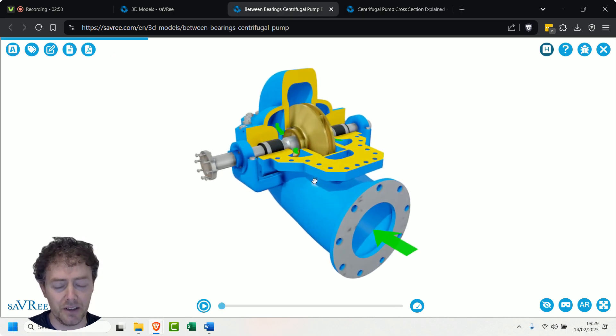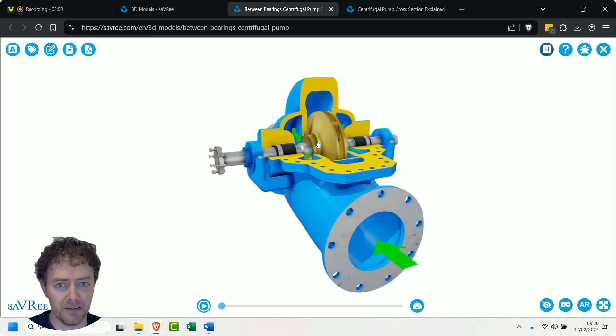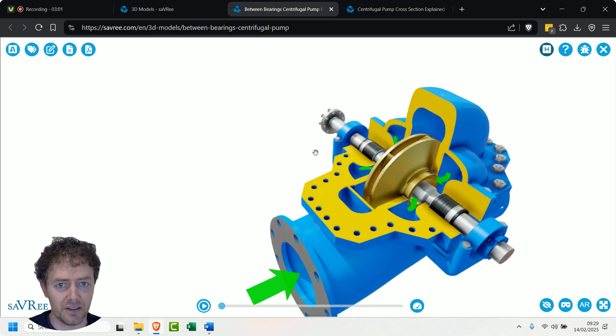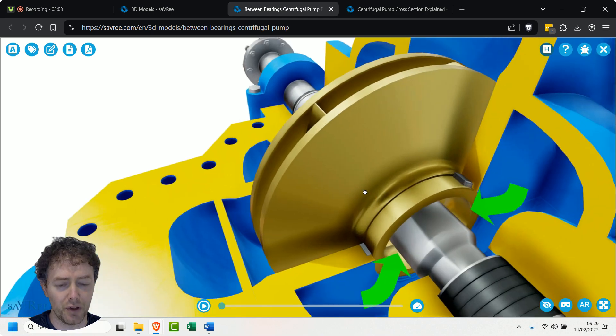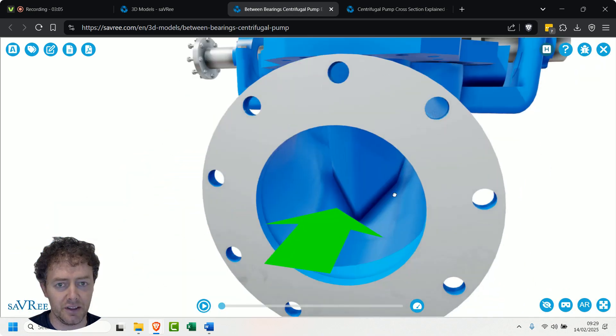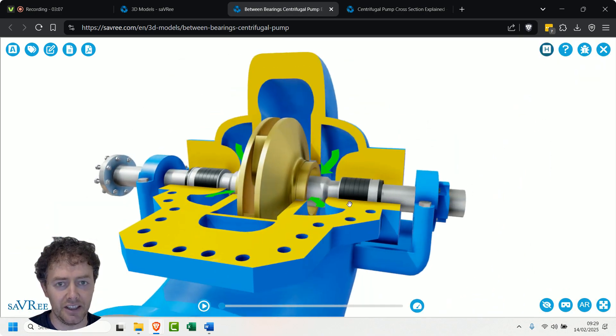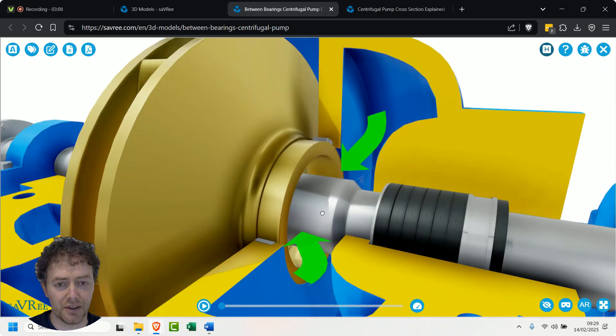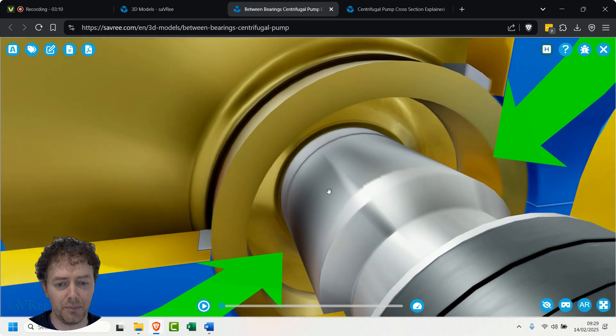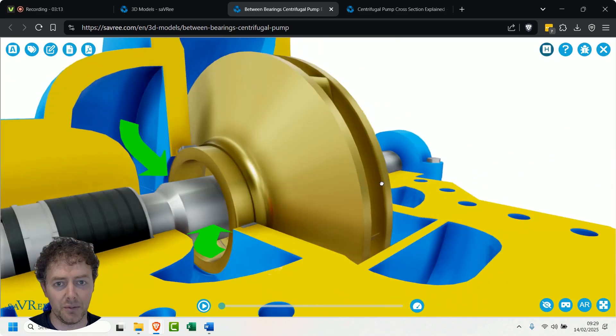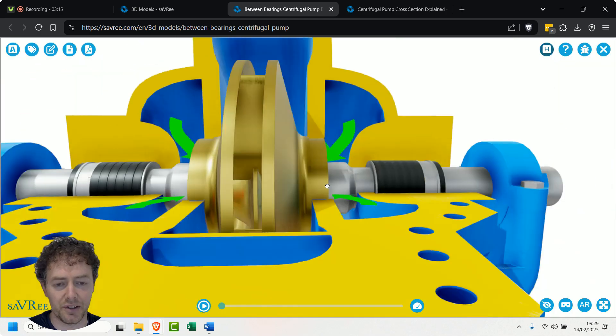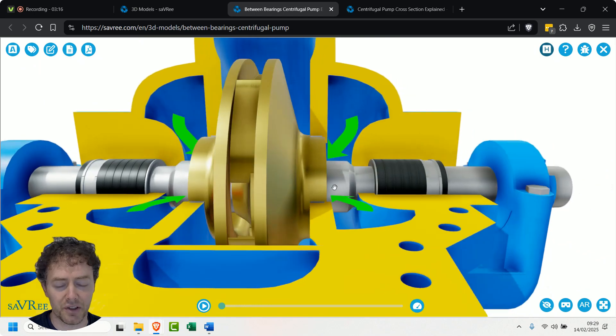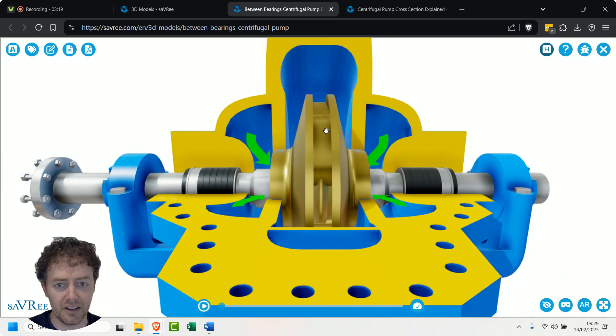So this is pretty much the same again. Let's have a look here - we've got the fluid comes in here, then it goes around the sides of the impeller, gets sucked into the impeller not just on that side but also on this side as well. So this is double suction, and then we're going to discharge it through the middle again.